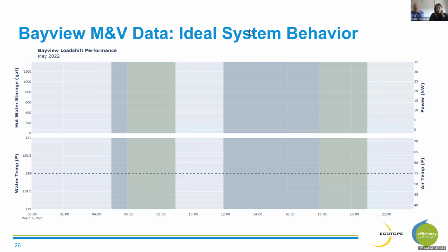At Bayview, we have around 70 monitoring points that we're collecting data on every single minute. So we can look at the system in really fine detail. So I'm going to show a little bit of our M&V data. This is how we evaluate load shift performance, how we see how the system is performing overall, and also how we can identify areas for system improvements. And so this particular day is from May 2022, where we saw some ideal system behavior that we want to be able to replicate all year long and in other buildings. This behavior is pretty representative of what we saw over the summer.